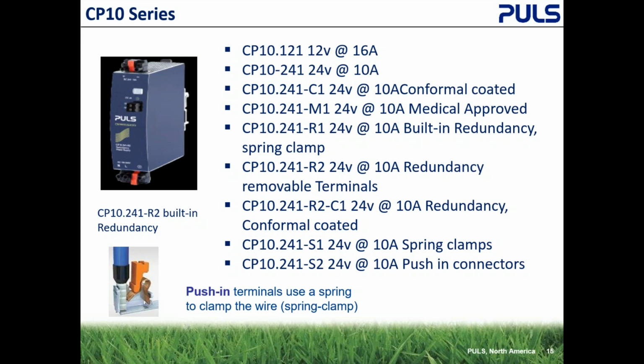So in the past, if you needed redundancy, some people would say, well, just put two power supplies in parallel to a load. That would work. However, if one power supply was short, you would lose that power supply, and the other power supply, putting all its load into a dead short, would turn itself off to protect itself. So in theory, you lost both power supplies. So that's why we had redundancy modules to take the one power supply that failed out of the circuit. This power supply has redundancy built in, so you would need two of these wired to your load.